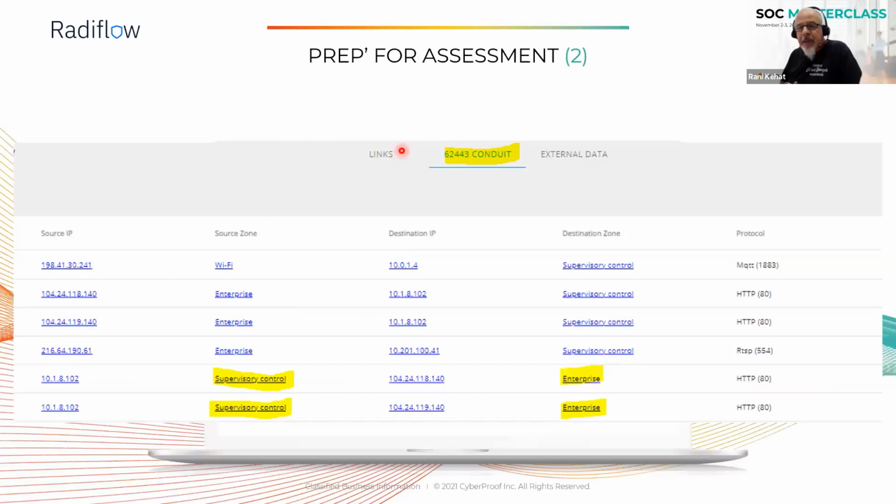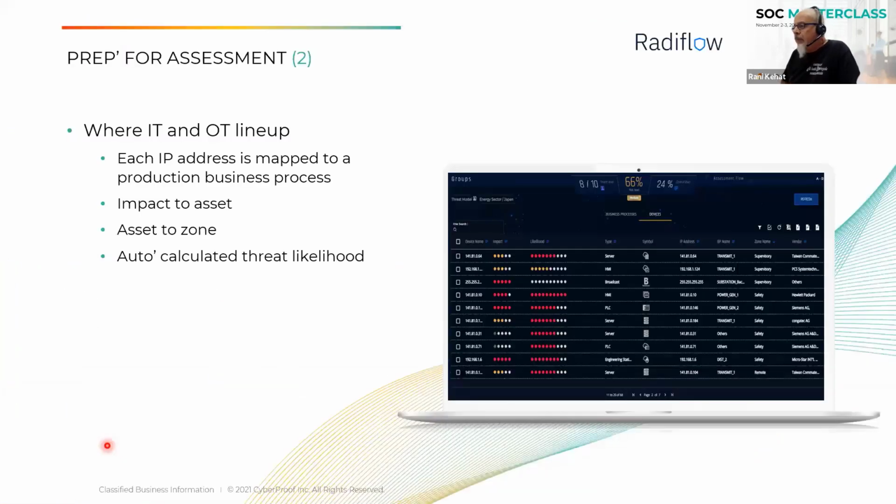Once we've done that, we can start dividing the network into the different zones. And from the zones, the system will automatically identify the conduits. Again, a very important aspect of understanding how to do SecOps. So when an alert comes up to the SOC, to the CDC, and it comes from a source that is a conduit, then obviously it will have a tag of higher priority because we need to look at these gateways between zones in a different way. And this is where IT meets OT.